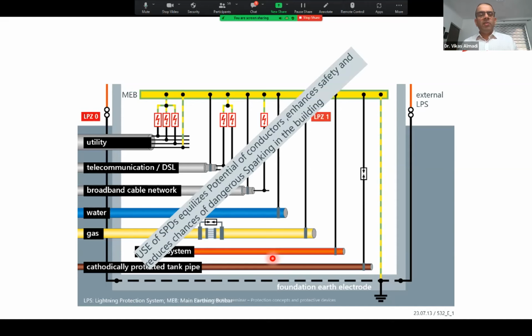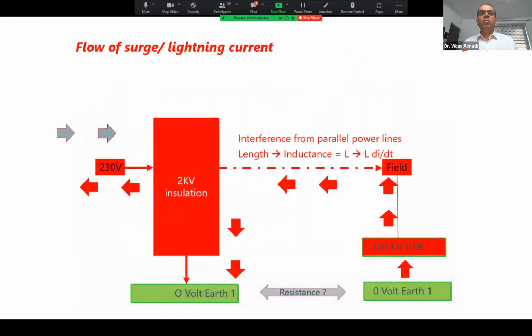sparking in the building. This is a fact, and you can see how the current would flow if there is a panel like this, and like some of you are into process industry, where basically long lengths of cables are there, and sometimes the earths are also kept separate, right? So normally if there is 0 volt, there is no problem. That means there is no fault, no problem. When there is a fault like lightning or any surge, then one of the earths will get a ground potential rise. That means the potential will rise from whatever normal voltage, like let us say 0, to some kVs, and this will appear across the field sensors, and then it will travel to the main control panels and try to go to the earth, but from there also it will still go to the other earth. So the looping will start. This is the natural phenomenon, and everything red here will get the damage. Depending upon the insulation, basically the things will start getting damaged.